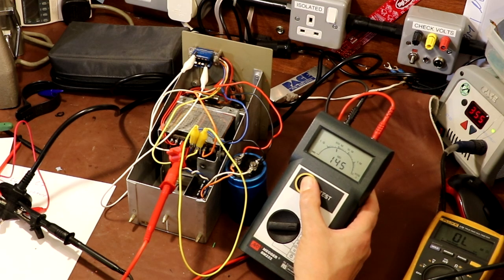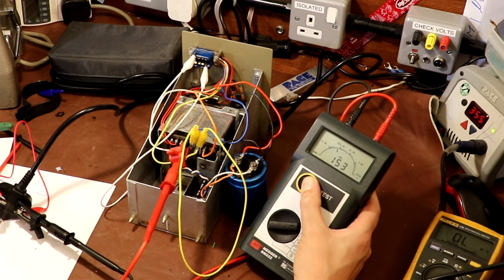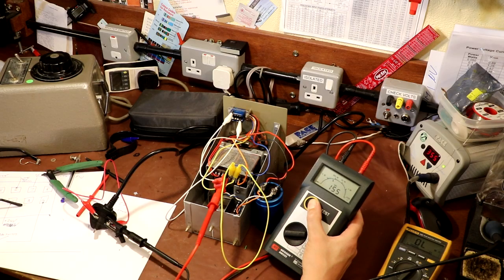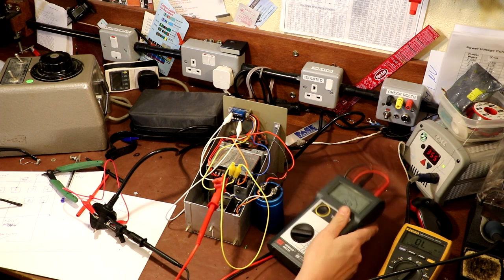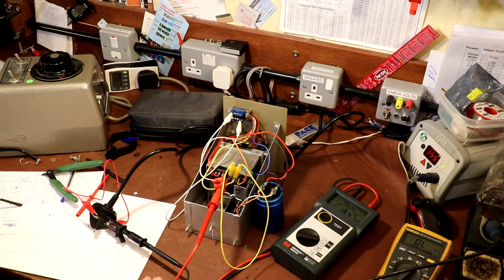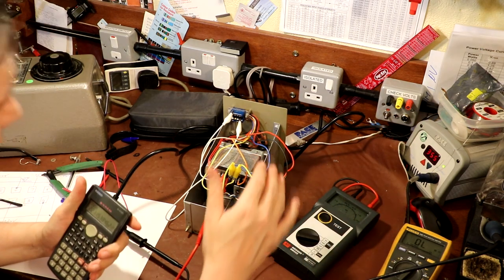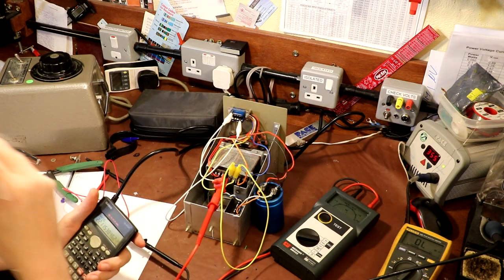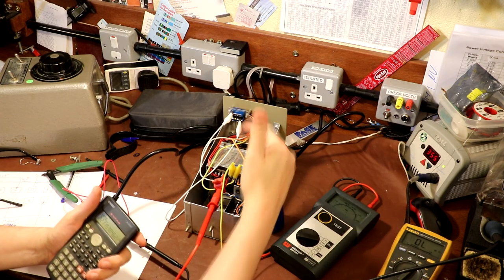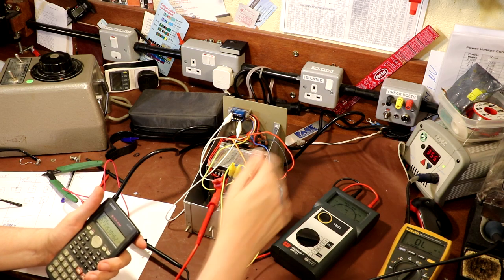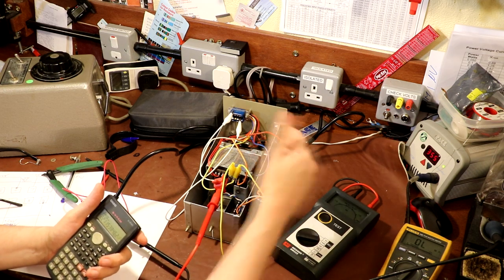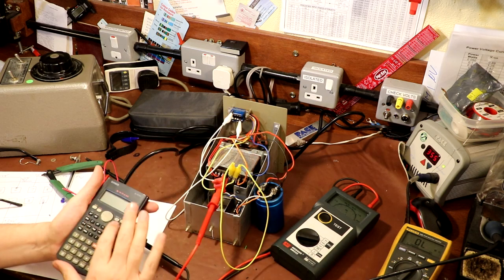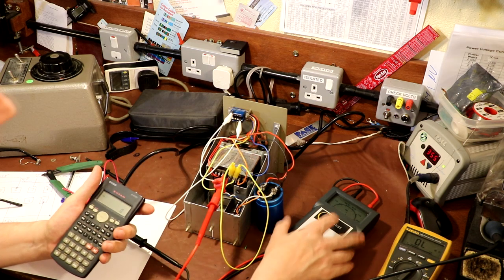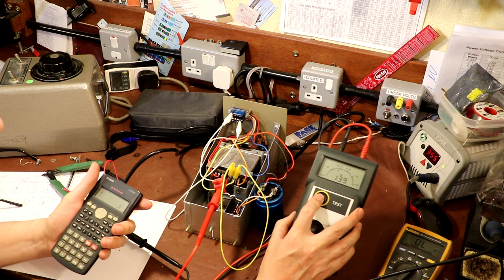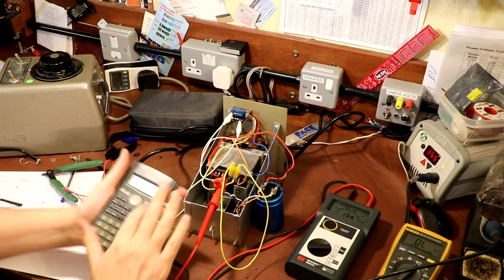Well, I'm going to say it comes up lower. It comes up a lot lower. It's coming up as around 150 megohm, and before the other transformer was coming up 1 gigaohm. So if we take that figure of 150 megohm of resistance, we've got a leakage between primary and secondary, and potentially to 0 volts, because the windings on the secondary are connected to 0 volts. We've got a maximum leakage there of, well, I've forgotten already. Was it 150 meg? Alright, I'm going to call it 140 megohm.